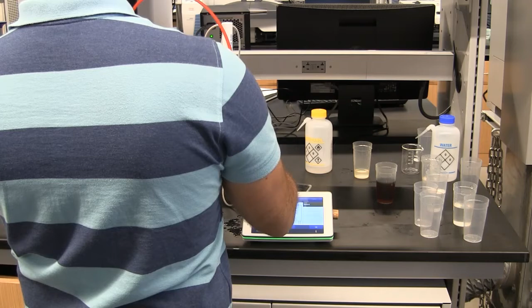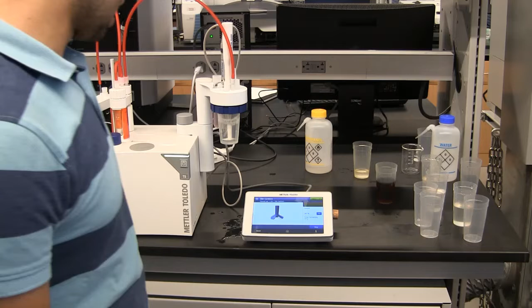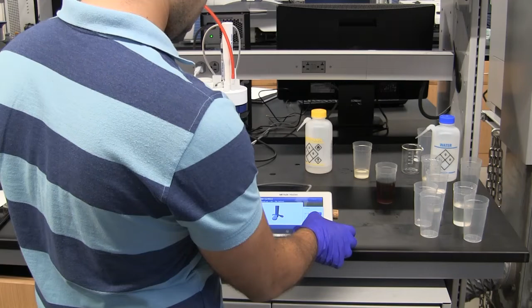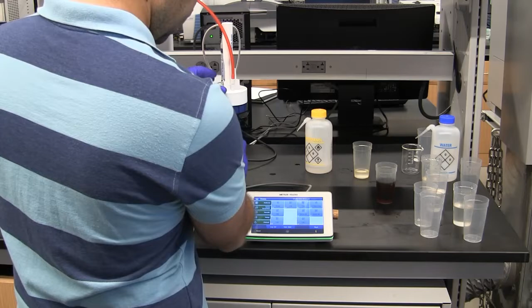So you go to manual, stirrer, and then you choose the stir time and speed, click start, and then it will stir everything. This way you make sure your pH sensor and everything is clean, and then you take it out and you rinse it with isopropanol followed by water. So it's done, click OK, you go back home, and then you remove your cup and clean one more time.